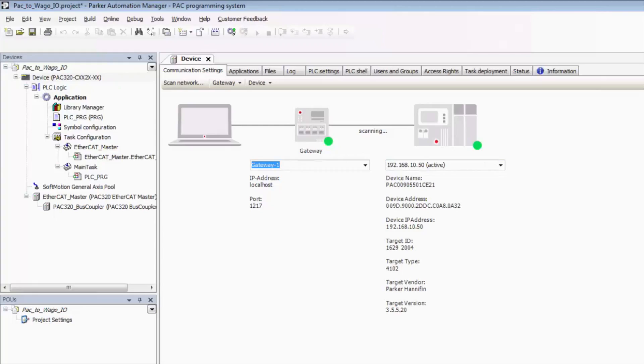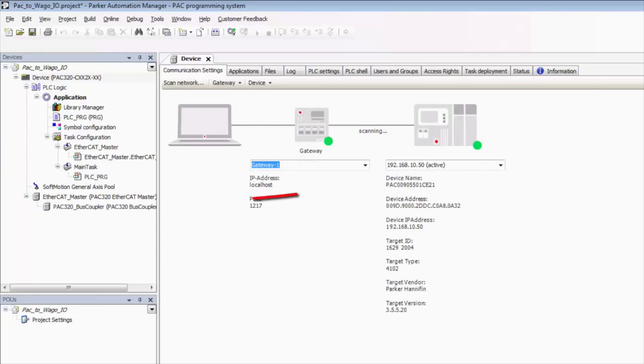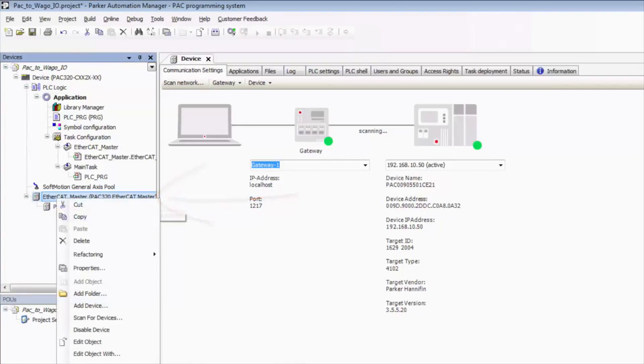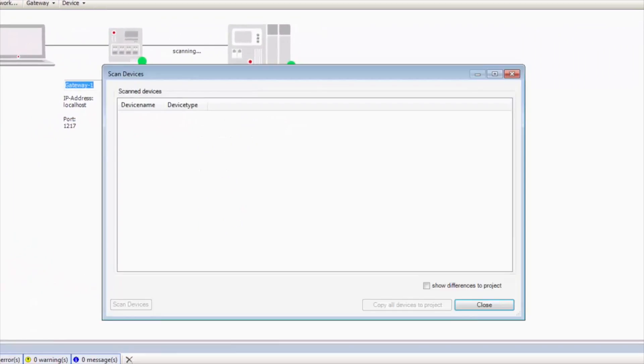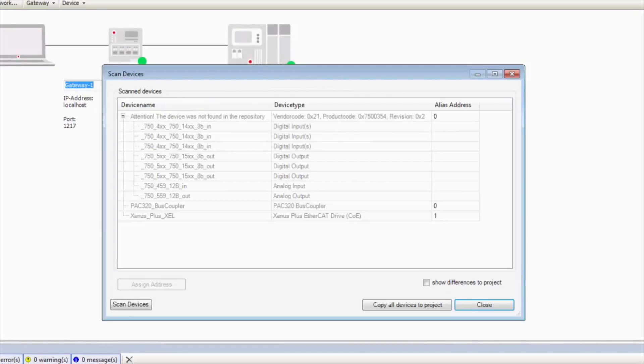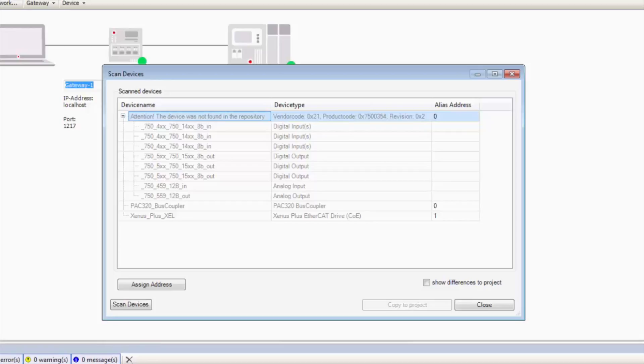From there we can go to EtherCAT master. We can right click and select scan for devices. So this should automatically find all EtherCAT devices on the field bus. We see right here this device is not in our repository. So that's actually our WAGO EtherCAT coupler.